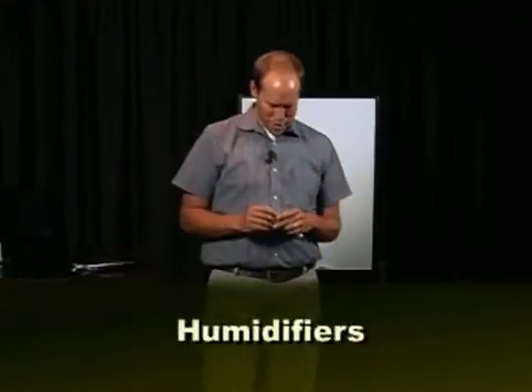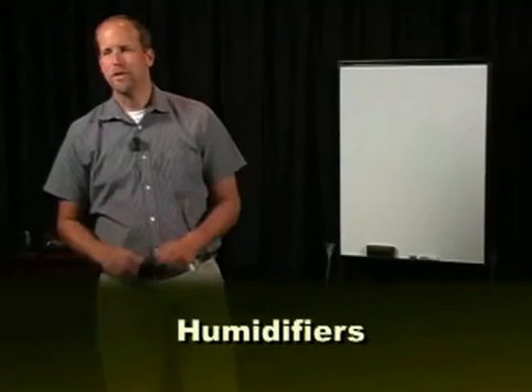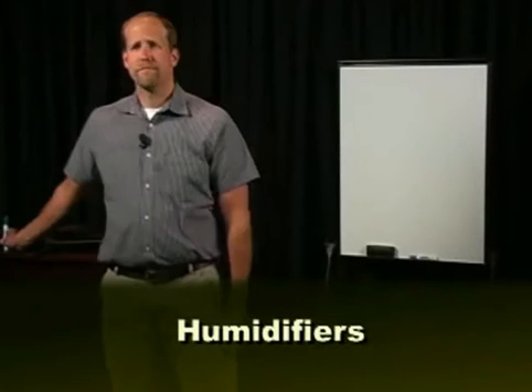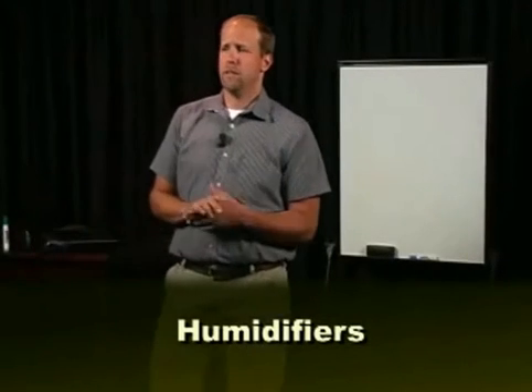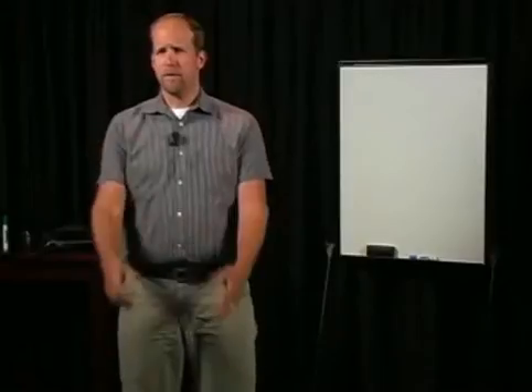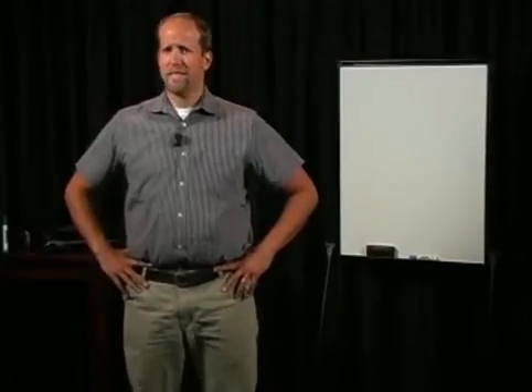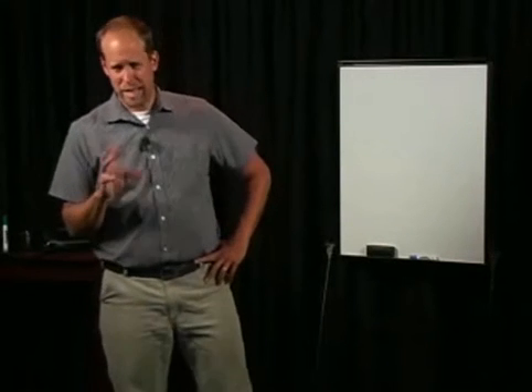Humidifiers. Moisture from humidifiers may support microbial growth on wet surfaces where moisture can condense during cold weather. Humidifiers that discharge small droplets of water from a reservoir of water are prone to supporting mold growth. Moisture accumulation inside a dirty ductwork creates a suitable environment for mold growth. The reservoir of a humidifier is usually contaminated to some degree. Humidifiers should be considered a potential mold growth source.